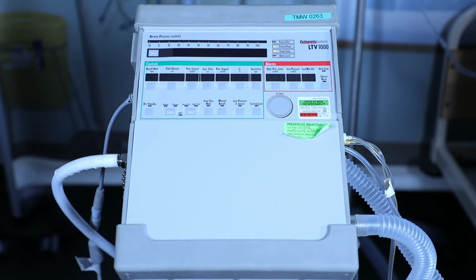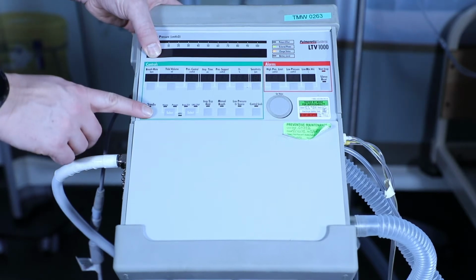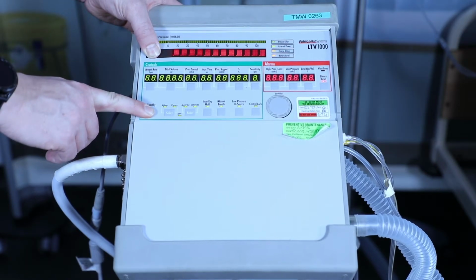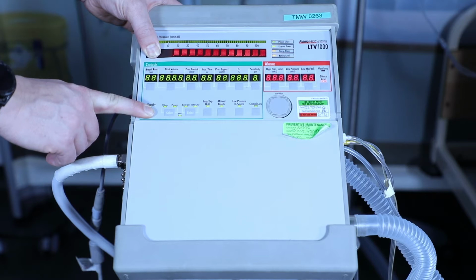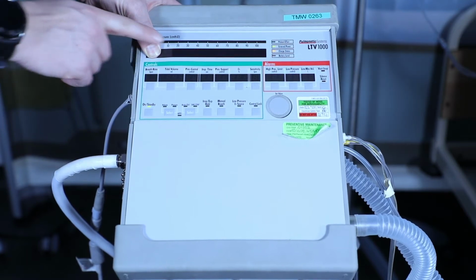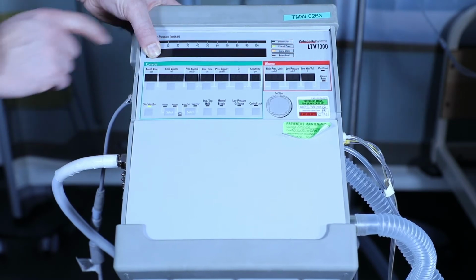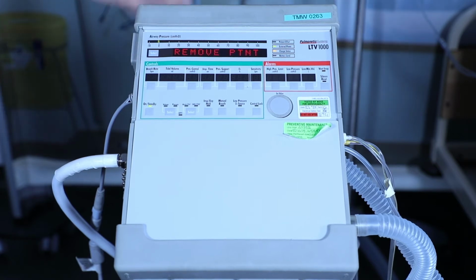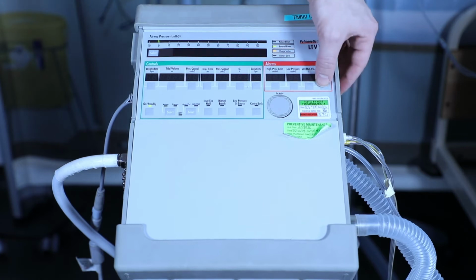Now that the component parts have been checked and reassembled, we want to check the function of the device. To switch the LTV on in test mode, press and hold the select button and press the on off button. Once remove patient appears on the display window, you can remove your finger from the select button. To silence this, press the silence alarm.